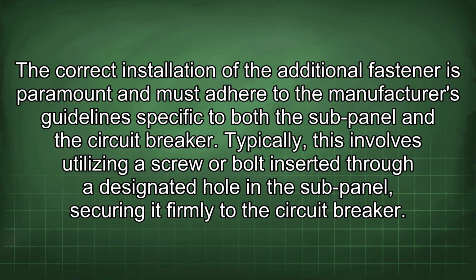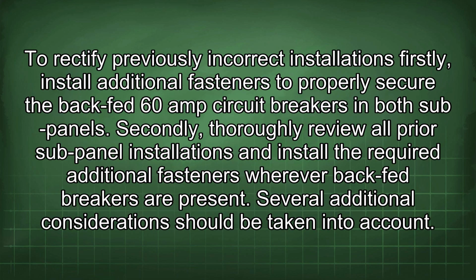Typically, this involves utilizing a screw or bolt inserted through a designated hole in the subpanel, securing it firmly to the circuit breaker. To rectify previously incorrect installations, firstly, install additional fasteners to properly secure the backfed 60-amp circuit breakers in both subpanels. Secondly, thoroughly review all prior subpanel installations and install the required additional fasteners wherever backfed breakers are present. Several additional considerations should be taken into account.